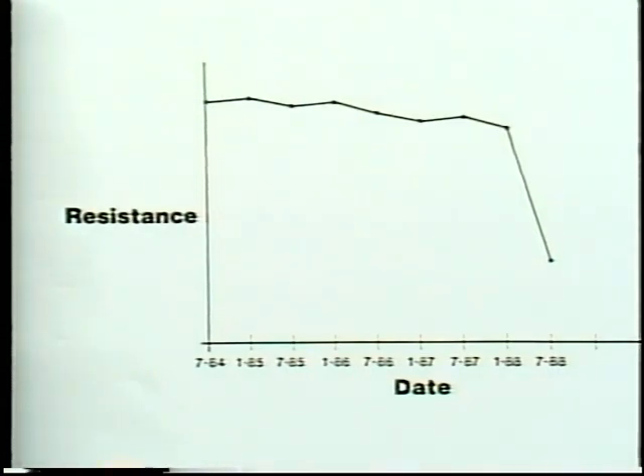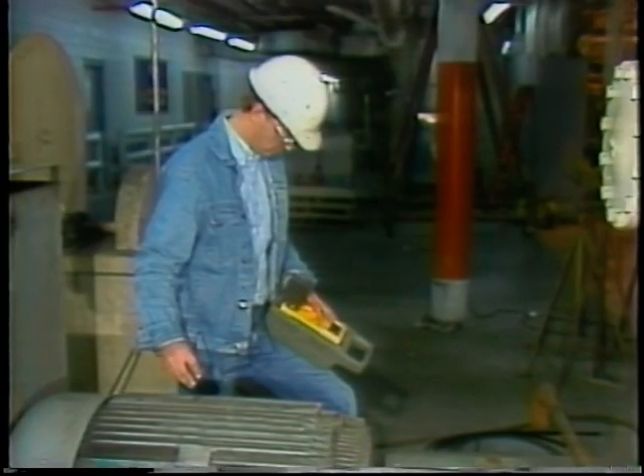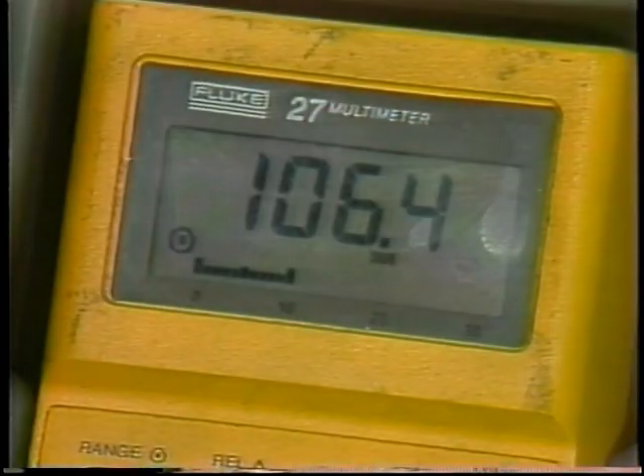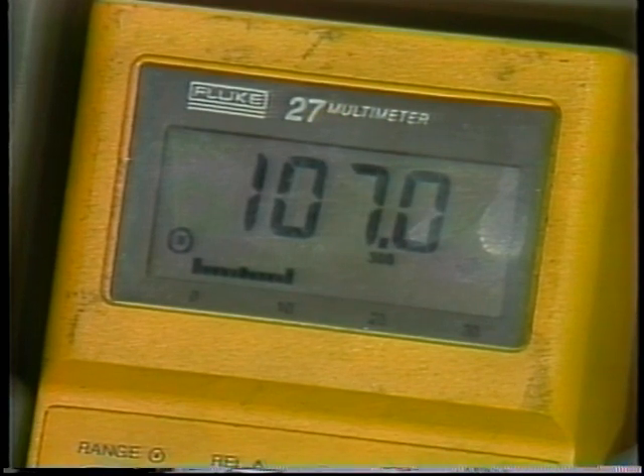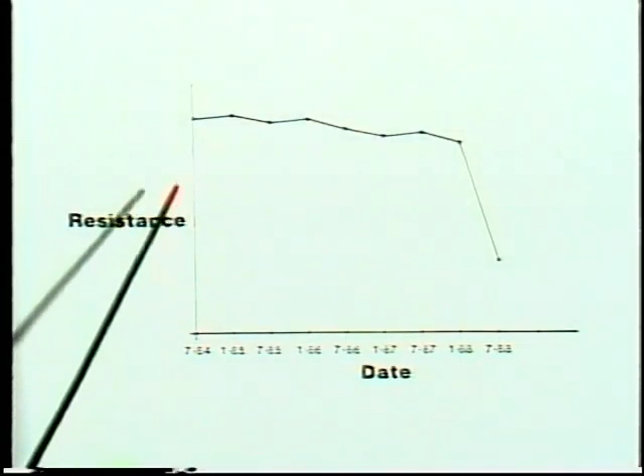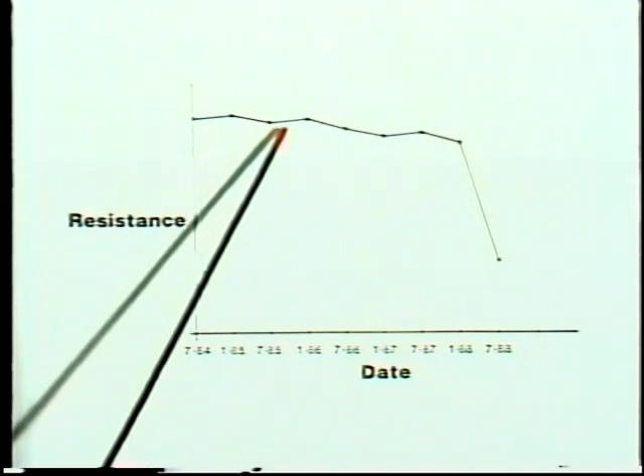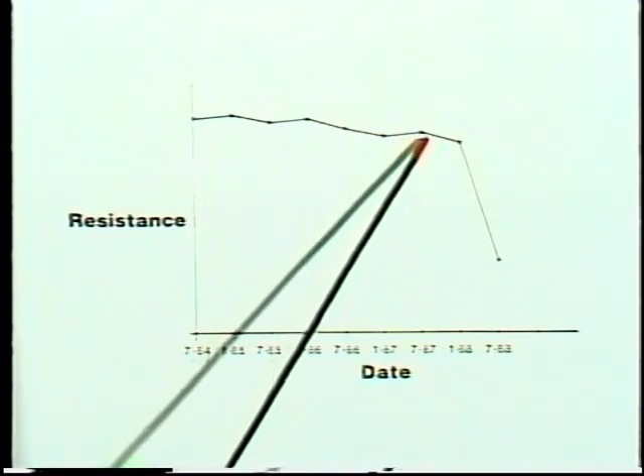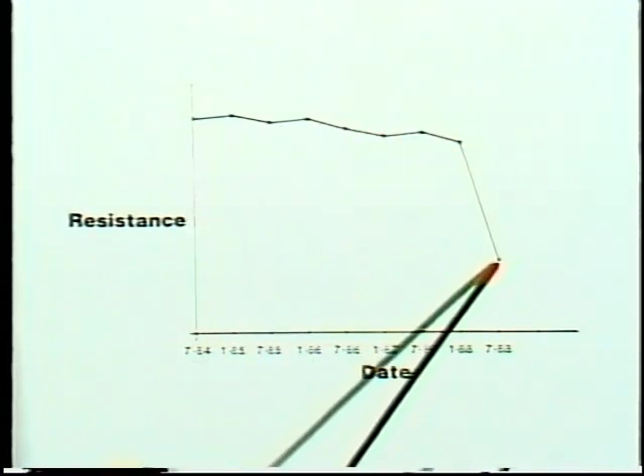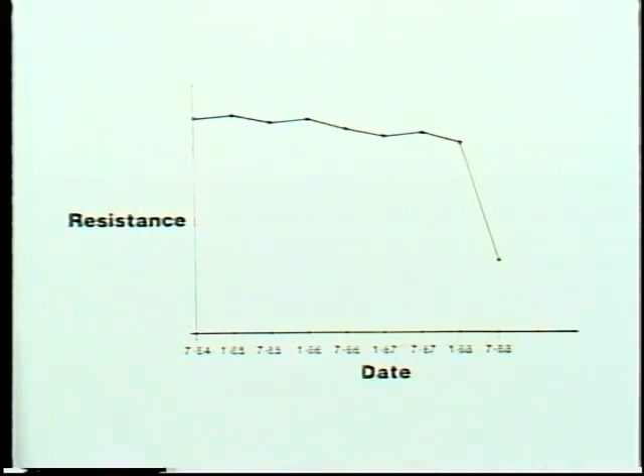Megohmmeter readings are most useful when they are taken regularly over the life of a motor. Ideally, they should be taken under the same temperature and humidity conditions or corrected for temperature and humidity. The readings will normally decrease slowly as the motor ages. If a new reading is much lower than the last reading taken a few months before, the motor should be watched carefully in the weeks or months ahead. If the readings continue to drop rapidly, plan to replace the motor.